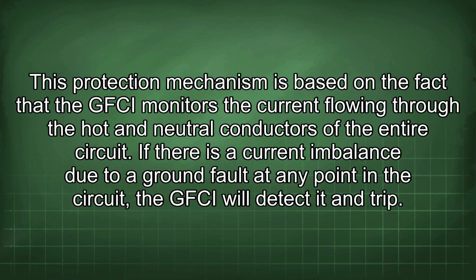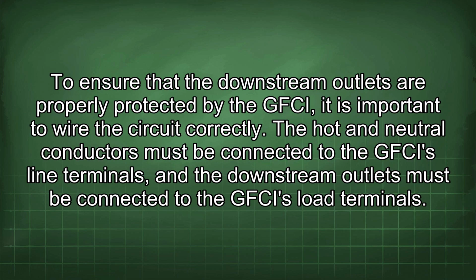This protection mechanism is based on the fact that the GFCI monitors the current flowing through the hot and neutral conductors of the entire circuit. If there is a current imbalance due to a ground fault at any point in the circuit, the GFCI will detect it and trip. To ensure that the downstream outlets are properly protected by the GFCI, it is important to wire the circuit correctly. The hot and neutral conductors must be connected to the GFCI's line terminals, and the downstream outlets must be connected to the GFCI's load terminals.